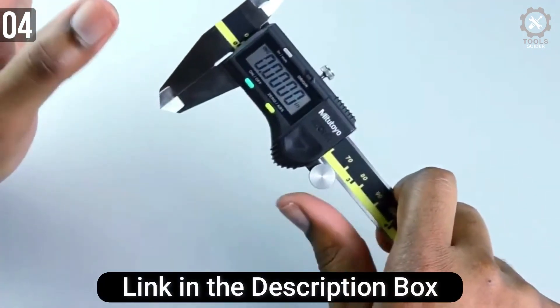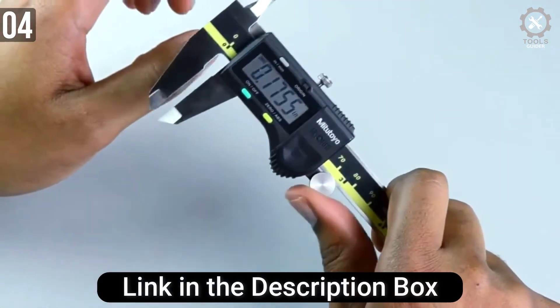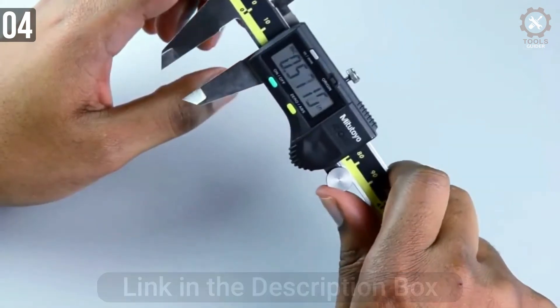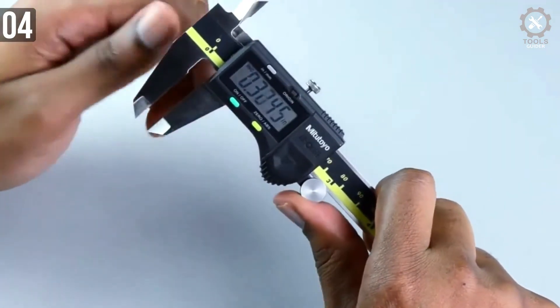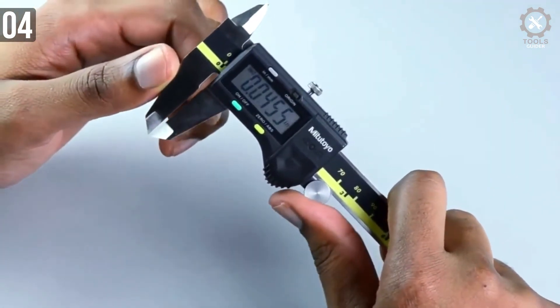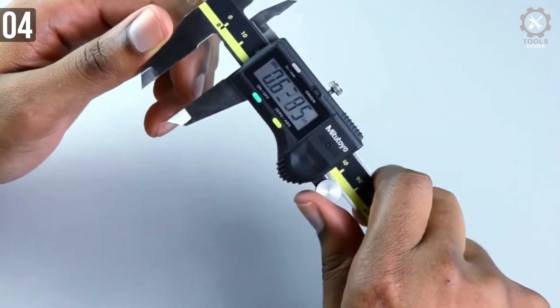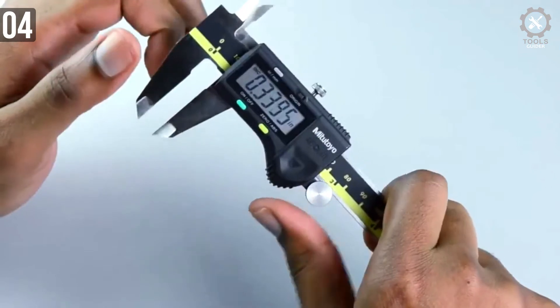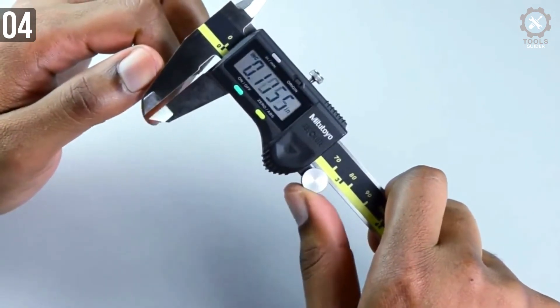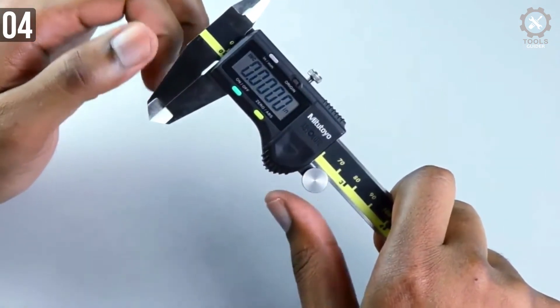You don't need to repeat zero setting anymore. The zero-slash-ABS key allows the display to be zero set at any slider position along the scale for incremental comparison measurement. This switch will also allow 500AOS return to the absolute coordinate and display the true position from origin point.